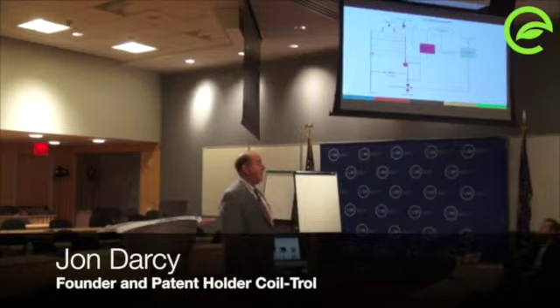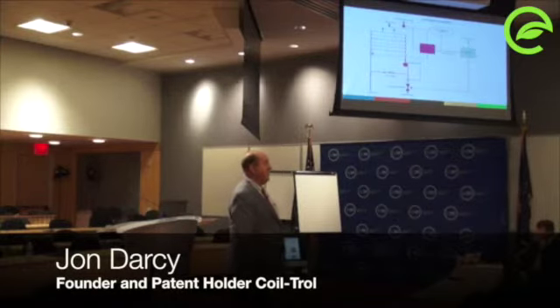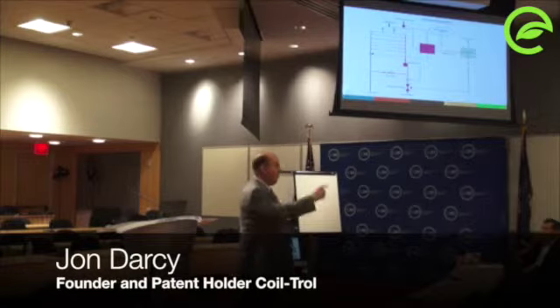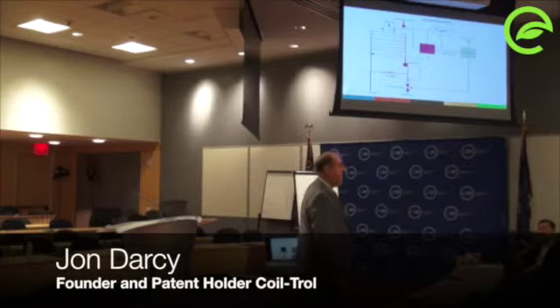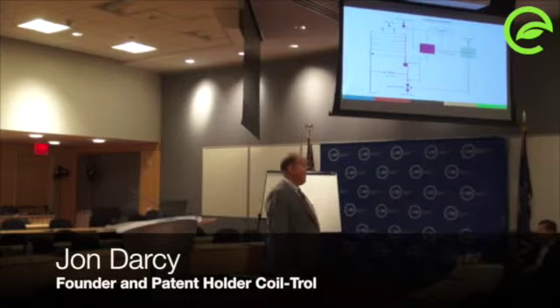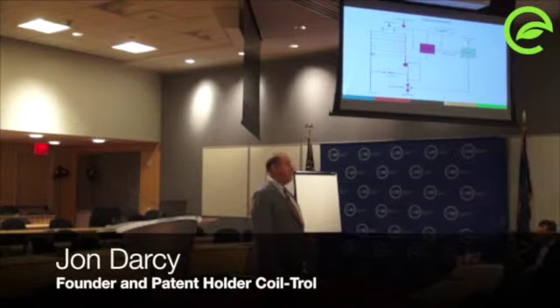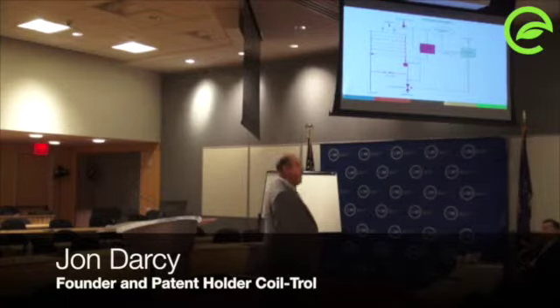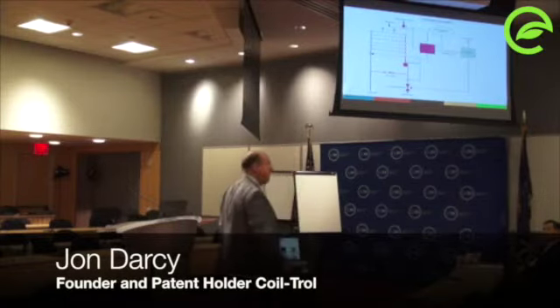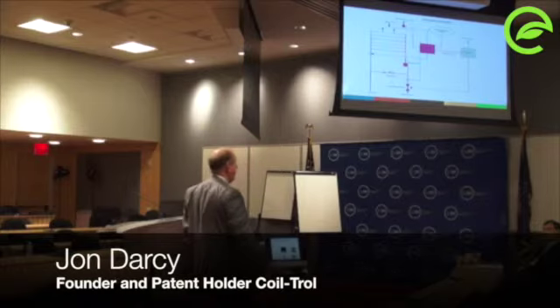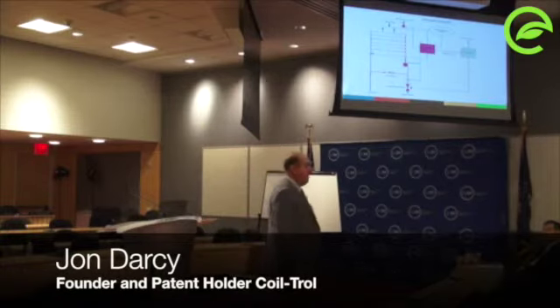You might have to jog it every once in a while because the water in it is eventually going to get too cold, but you might have to jog it every once in a while or run it at some very reduced level just to keep the water moving through the system. But that will pretty much stop you from freezing. That pump will pretty much stop you from freezing that coil. It's simple, it's not expensive, and it has a great payback.